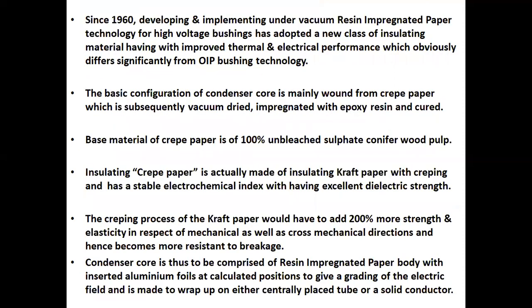Since 1960, developing and implementing under-vacuum resin impregnated paper technology for high voltage bushings has adopted a new class of insulating material having improved thermal and electrical performance, which obviously differs significantly from oil impregnated bushing technology. The basic configuration of the condenser core is mainly wound from crepe paper, which is subsequently vacuum dried, impregnated with epoxy resin, and cured.